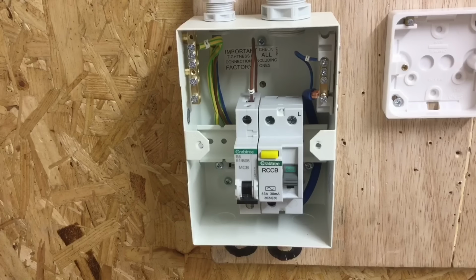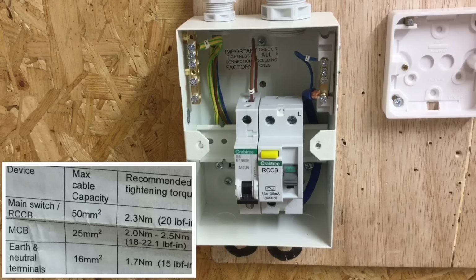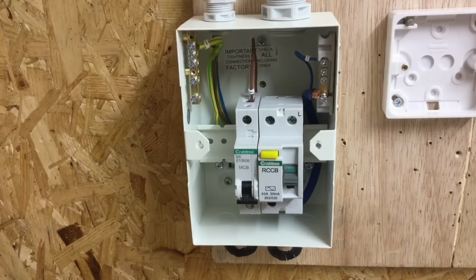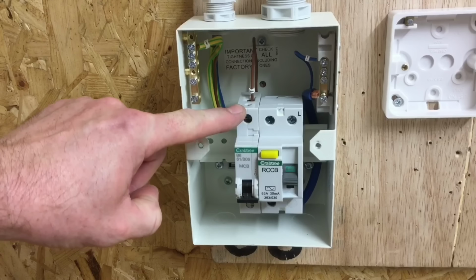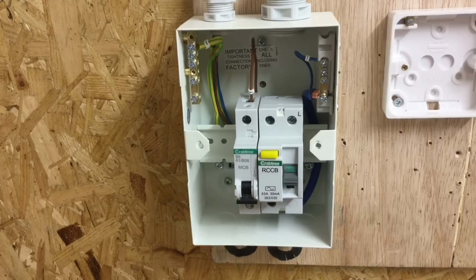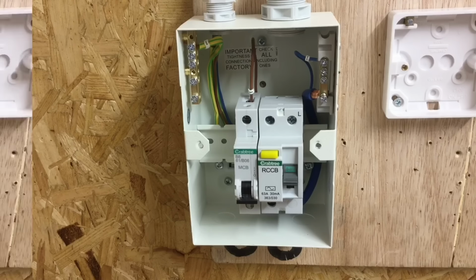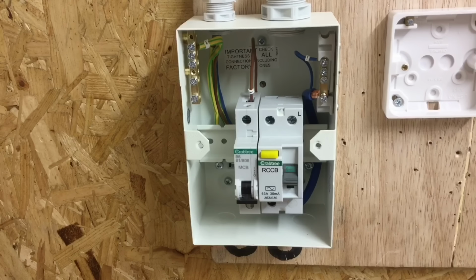We've used the manufacturer's instructions to get the required Newton meters of torque for both the neutral bar and the earth bar, which are identical at 1.7 Newton meters. We've got the appropriate torque setting for the top of a circuit breaker. In this case, I've set it to 2.4 Newton meters of torque, and our distribution board is now ready for our first test. And the first test we're going to carry out is continuity of CPC and polarity. After that test, we're going on to carry out the insulation resistance test of our one-way lighting circuit.